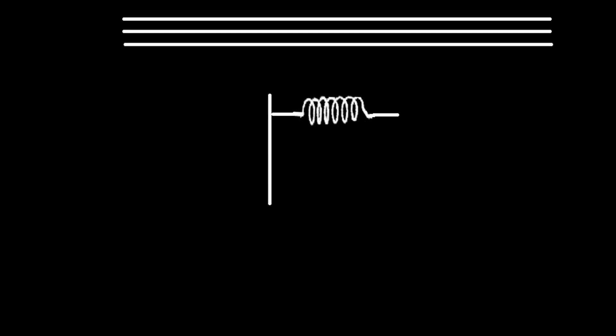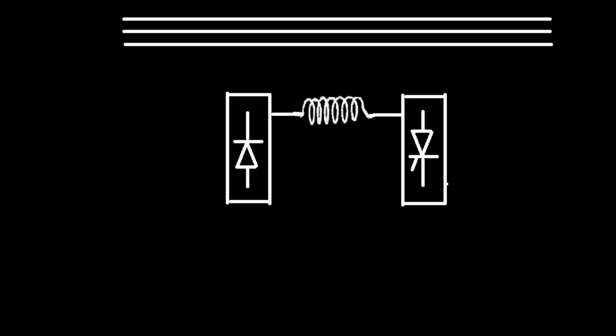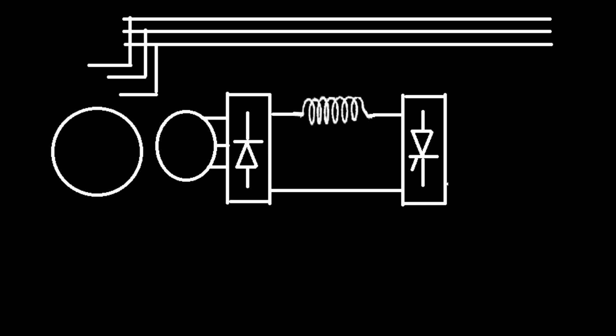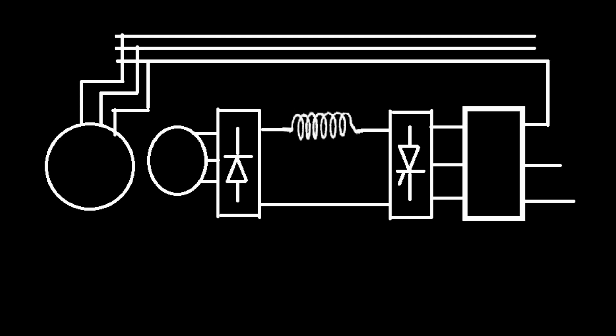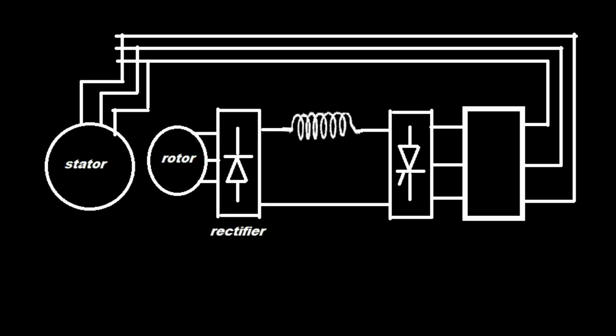The slip energy recovery scheme basically consists of a rectifier, reactor, converter, and transformer. The rectifier is connected to the rotor, which converts AC to DC and forces the power to flow away from the winding. The reactor is used to smoothen the current. The phase-controlled converter is used in inversion mode as an inverter for converting DC to AC. The transformer is used to improve the power factor.